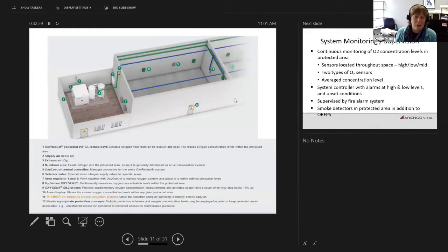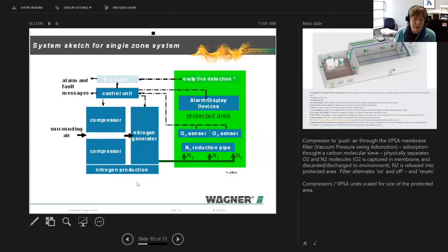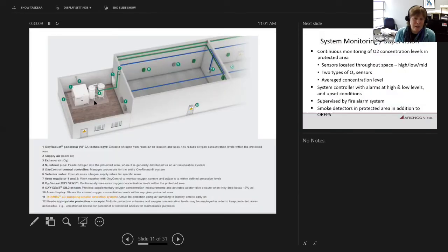Again, another image borrowed from Wagner. This is just a schematic, kind of showing conceptually, you'd have a physical plant. It would be quite similar to a fire pump room where you have all your equipment. You'd have your compressors, you'd have your membranes, you'd have your control unit, and it's sitting, in most warehouses we're dealing with, our cold storage. So it's sitting in a room separate from the protected area. It was at ambient conditions, and it's not dissimilar to any mechanical service space. Again, a fire pump room or an HVAC area.